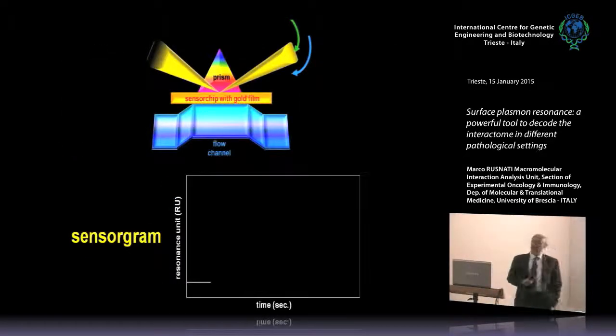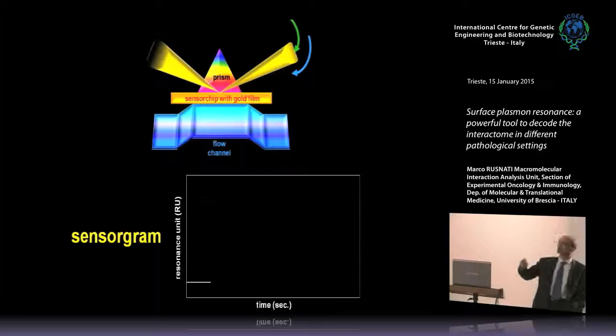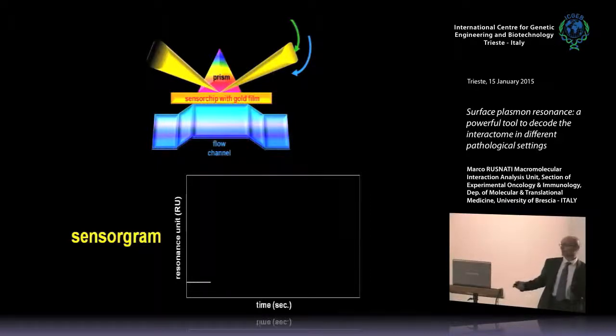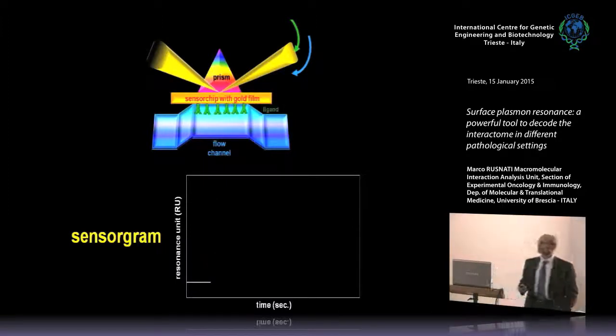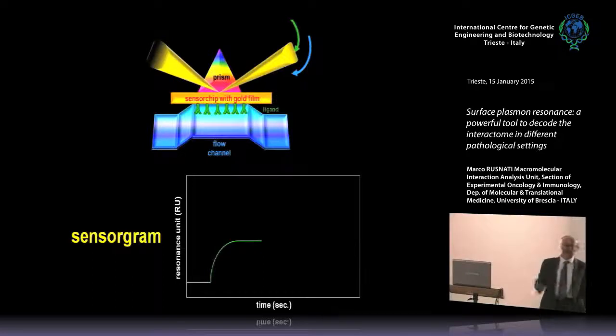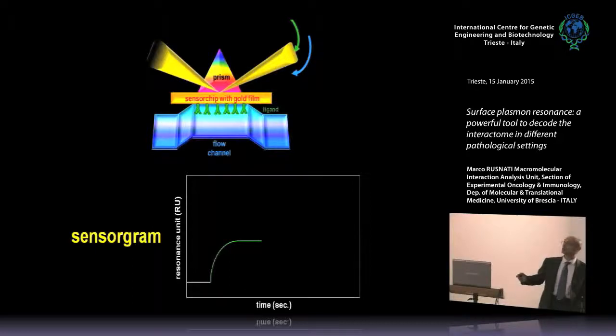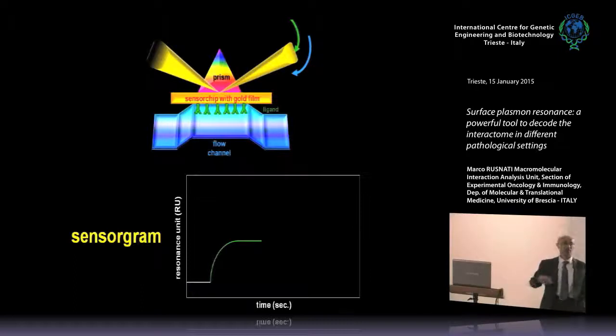In the SPR apparatus there is embedded software that transforms this modification of the resonance angle of the refractive index into something that we call a sensorgram. A sensorgram is a graph in which, as a function of time, we report the increase of resonance units bound to the sensor chip — bound to the gold film. When we immobilize the first molecule, the ligand, we observe an increase of RU units that is irreversible, because the immobilization of the ligand to the gold film is obtained chemically and is irreversible. So we have generated a new baseline.